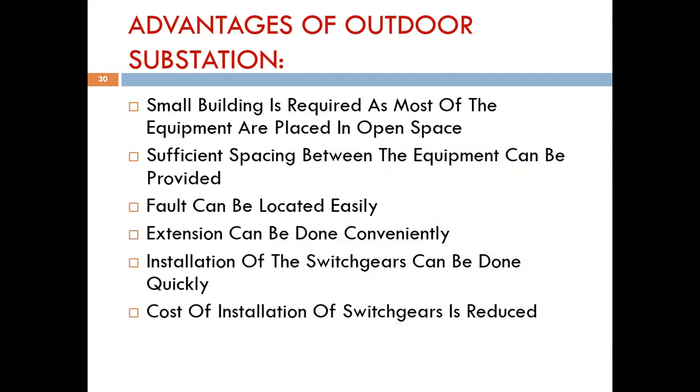A small building is required, as most of the equipment is placed in open space. Sufficient space between the equipment can be provided. Faults can be located easily. Extension can be done conveniently. Installation of switchgear can be done quickly, and the cost of installation of switchgear is reduced. These are the outdoor substation's advantages.